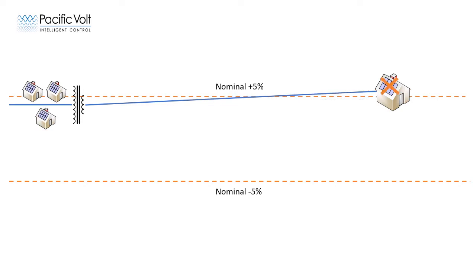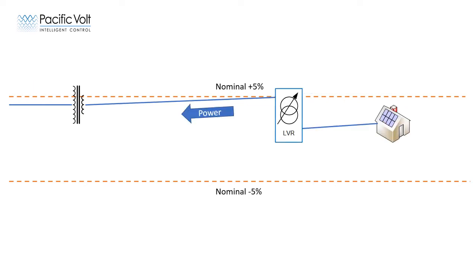Unless the voltage on the medium voltage feeder can be reduced, the voltage at some of the buildings will begin to exceed the maximum limit and their PV inverters will shut off. This is typically more of an issue towards the end of a radial feeder at midday. If the medium voltage can't be reduced because it is needed to support a large load at the end of the feeder, inserting an LVR will lower the voltage at the building while also allowing the power to flow back onto the grid.